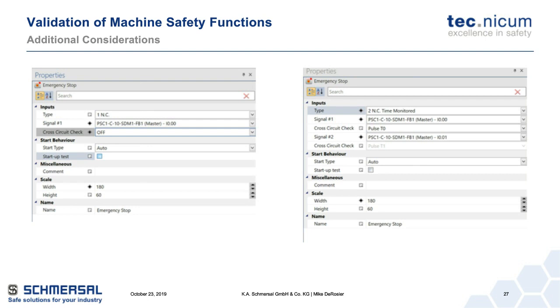Why is all of this important at the end of the day? I have several examples of projects I worked on with customers where I went into either the end user to look at a piece of equipment that was supplied and perform validation, or got involved right from the OEM from the get-go before the FAT came in to do the validation testing, and we did these functional tests. I know of 3 separate occasions where doing that functional testing found issues as a result.